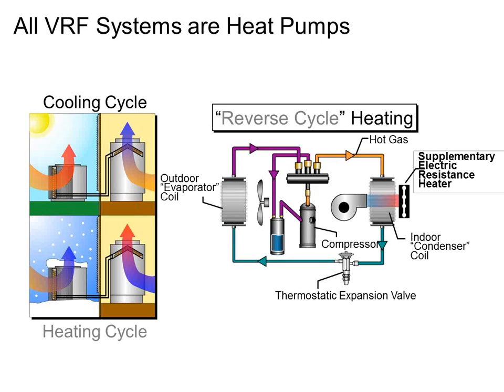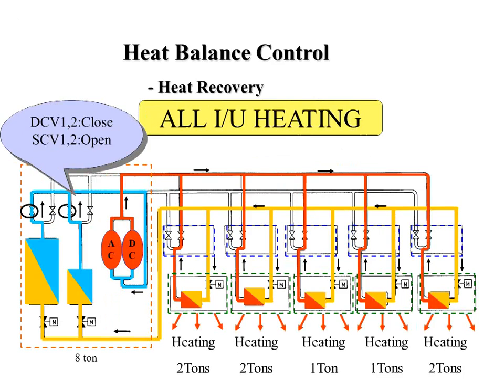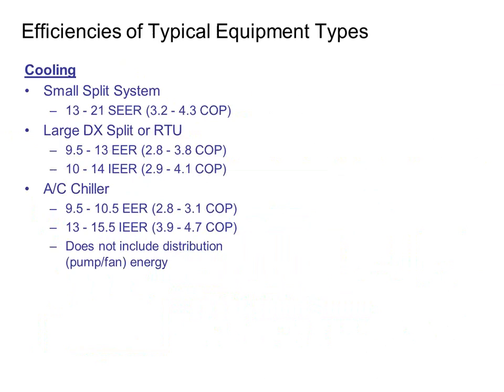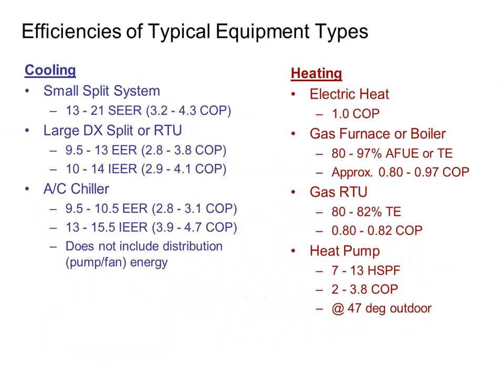They move it from outside to inside, just like your air conditioner does. Your air conditioner moves heat from in your house to outside your house. The heat pump moves heat from outside to inside. So on those really cold days in the winter, it's 10 degrees out or whatever, I'm looking for the heat that's available outside. I'm sucking it into my coil outside, and I'm pumping it into your building. Because I'm only paying to move the heat and I'm not paying to make the heat, it is significantly more efficient than 100%. In all cases, for all heat pumps, at all outdoor ambient conditions that you would experience in the Midwest. Now, if you go to the Arctic, okay, maybe this isn't true anymore, and maybe you do get below 100% efficient, but for everything else, the heat pump is going to be above 100% efficient, and it's always going to beat out the electric resistance heat.